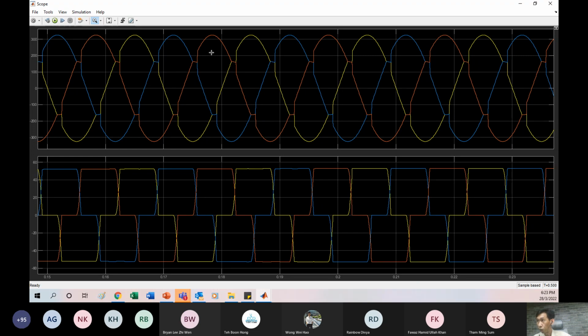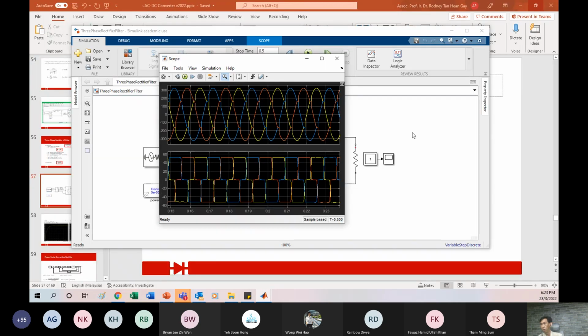Again, when the voltage and current draw differently from each other, that means it's a non-linear load, so it will cause harmonics to the grid side. It depends on the power level — for LV there's no issue, a lot of LV systems don't have this problem, but for MV you have to be very careful.